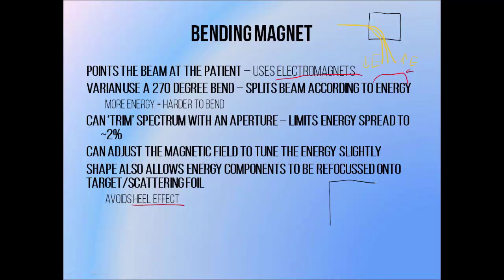Linacs produced by Varian Medical Systems tend to use a 270-degree bending magnet instead, so it moves the incident electron beam through three quarters of a circle in order to point it at the patient rather than just a 90-degree bend. This does separate the beam somewhat according to energy, but the 270-degree bending design allows us to refocus these components onto one point on the x-ray target or electron scattering foil. So there is no heel effect and they are focused on a very small point, which allows us to obtain a very sharp beam edge.